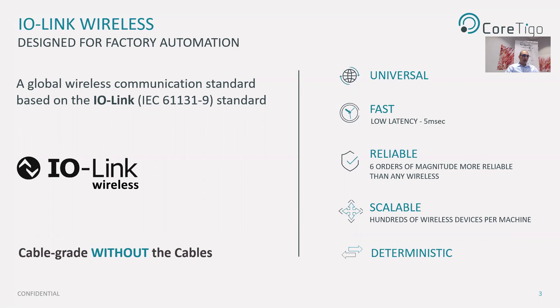IO-Link Wireless ensures a low latency of five milliseconds and very high reliability, measured by the packet error rate. It is a million times more reliable than conventional wireless networks such as Wi-Fi, Bluetooth, ZigBee, or Wireless HART. In addition, the IO-Link Wireless protocol is designed to be very robust — it coexists with other wireless systems in range and is very immune to noisy and harsh environments such as factory automation environments.